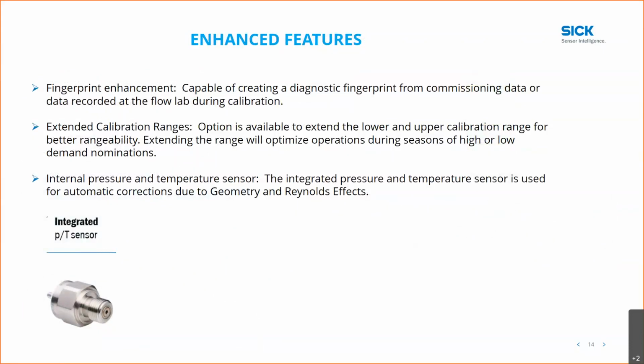Fingerprint enhancement is another one that's available. Real quickly, you're capable of creating diagnostic fingerprints from the commissioning data or from data that was recorded at the flow lab during calibration. Another option that you have now is extended calibration. This is an option to extend the lower and upper calibration ranges for better rangeability. Extending the range will optimize operations during seasons of high or low demand.